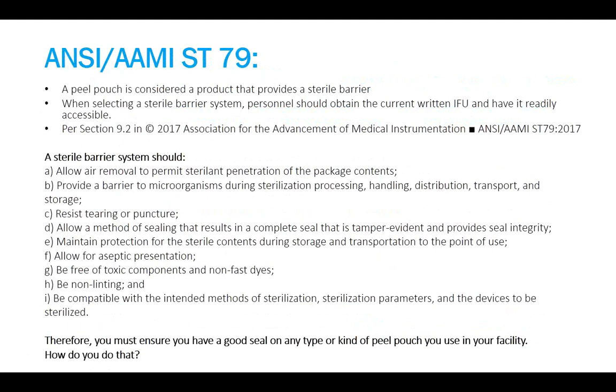Look at puncture resistance, how it seals, whether it allows air removal, aseptic presentation, and whether it's compatible with the intended method of sterilization. Remember, in the first few slides I talked about picking the pouch to match the type of sterilization — if you have low temperature sterilization, you would not use paper-plastic pouches. You want to use those suited to the modality you're using. Therefore, you must ensure you have a good seal on whatever type of pouch you use in your facility. How do you do that? I'm going to get to the meat of this program now.